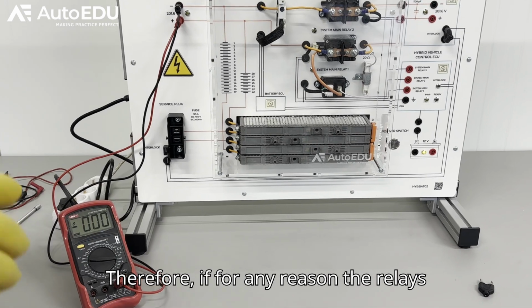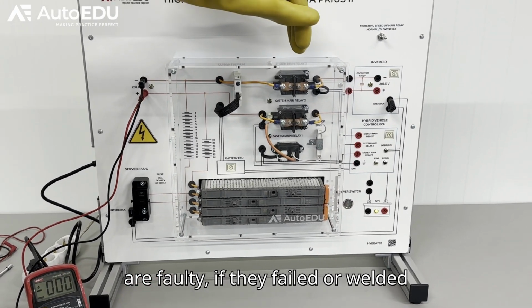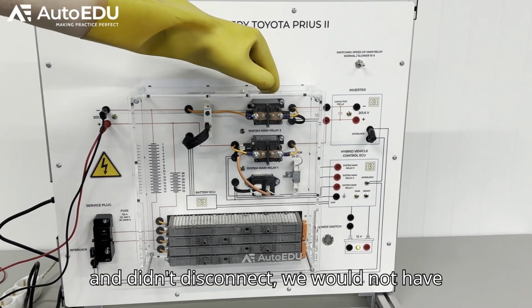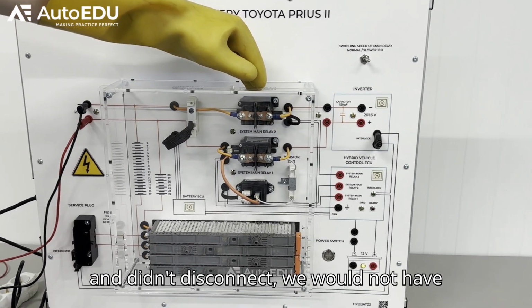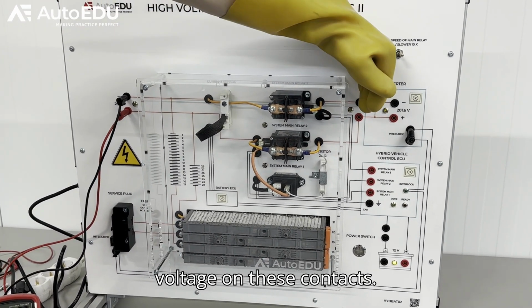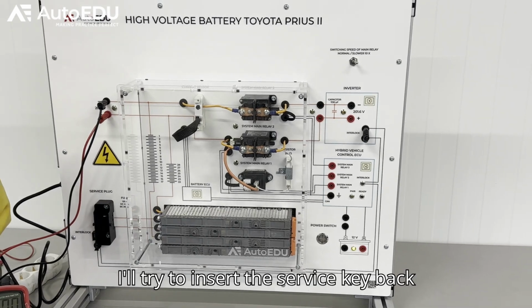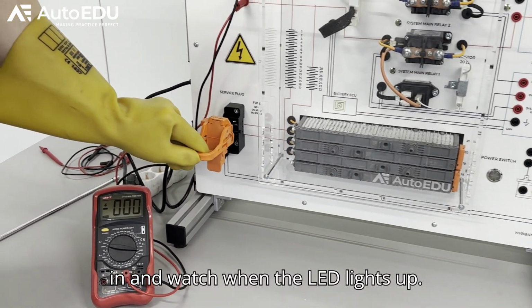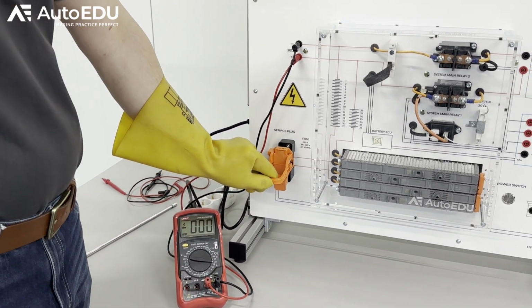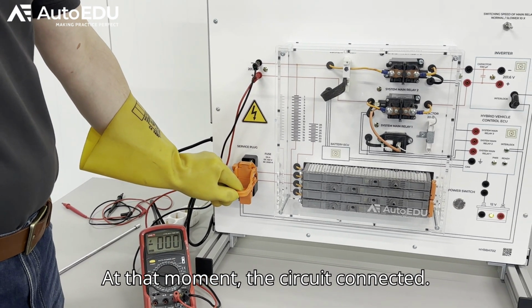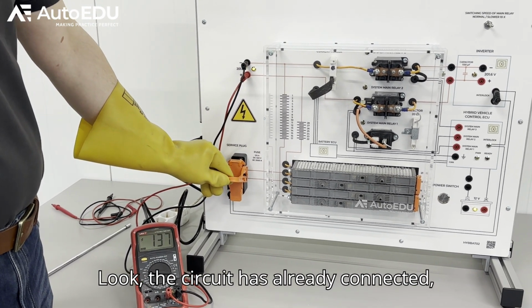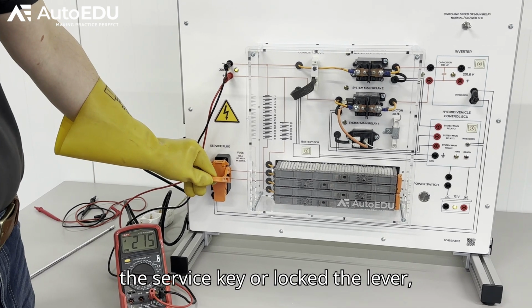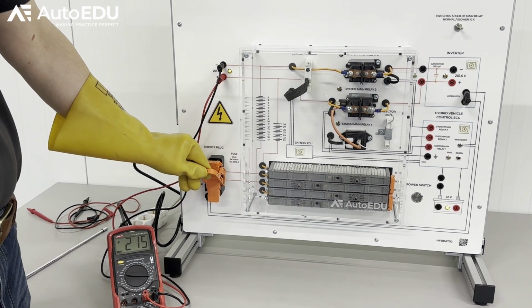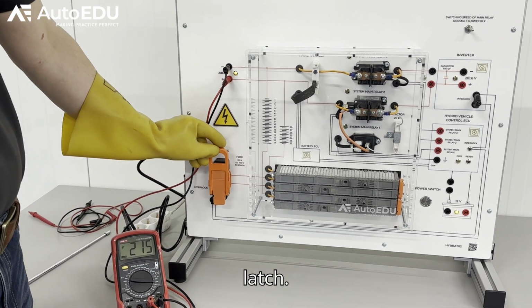Therefore, if for any reason the relays are faulty, if they failed or welded and didn't disconnect, we would not have voltage on these contacts. I'll try to insert the service key back in and watch when the LED lights up. At that moment, the circuit connected. Look, the circuit has already connected even though I haven't yet fully inserted the service key or locked the lever, connected the interlock, and locked the latch.